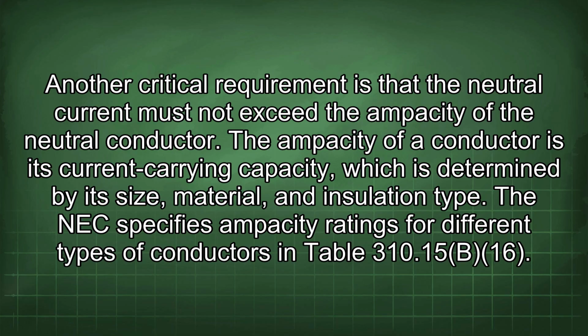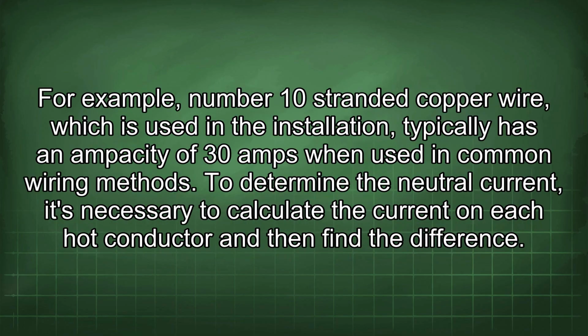Another critical requirement is that the neutral current must not exceed the ampacity of the neutral conductor. The ampacity of a conductor is its current carrying capacity, which is determined by its size, material, and insulation type. The NEC specifies ampacity ratings for different types of conductors in Table 310.15(B)(16). For example, number 10 stranded copper wire, which is used in the installation, typically has an ampacity of 30 amps when used in common wiring methods.